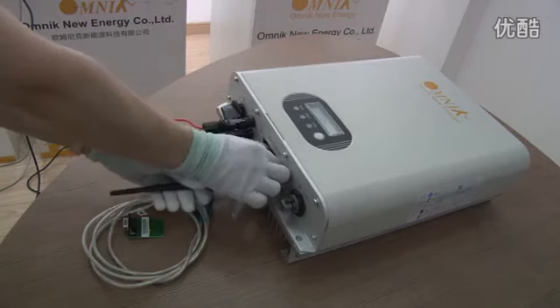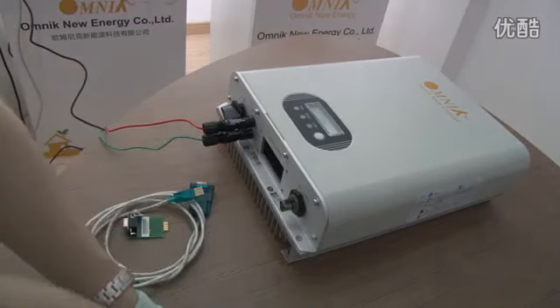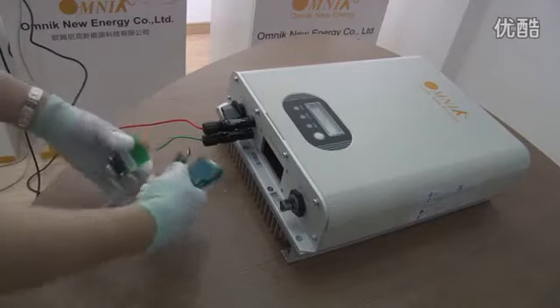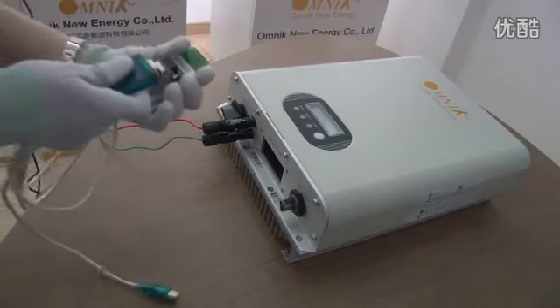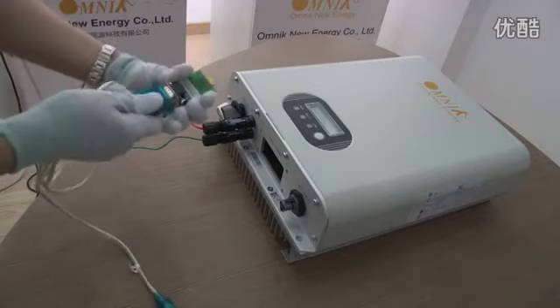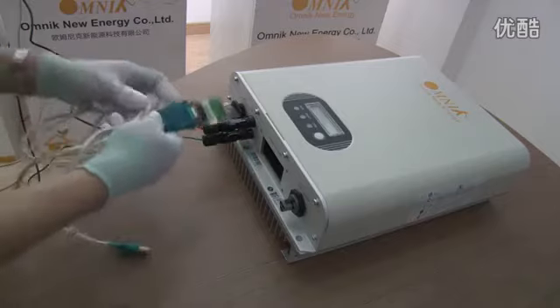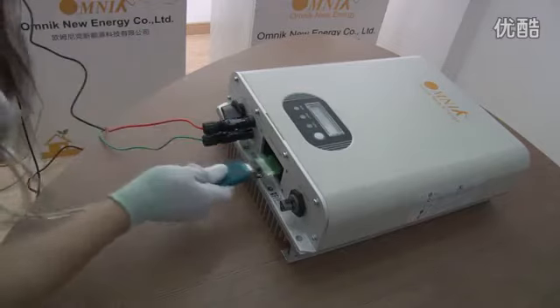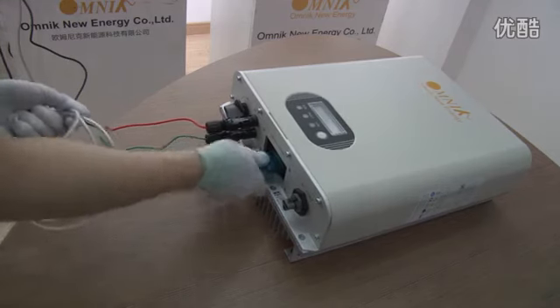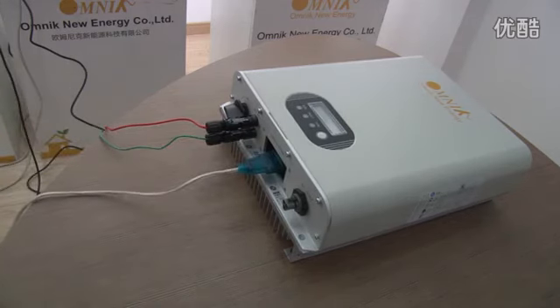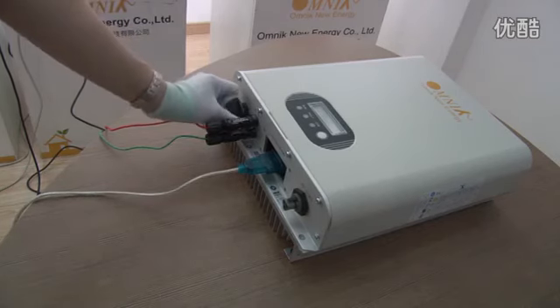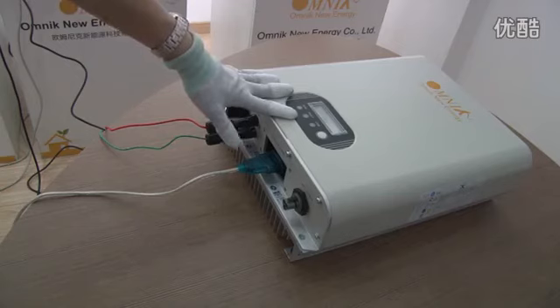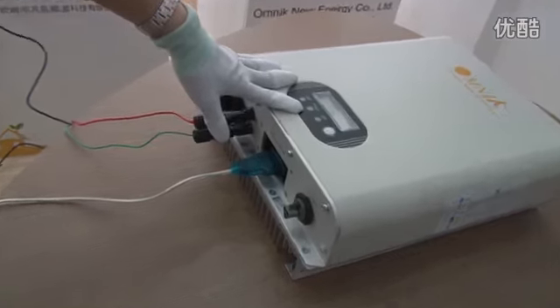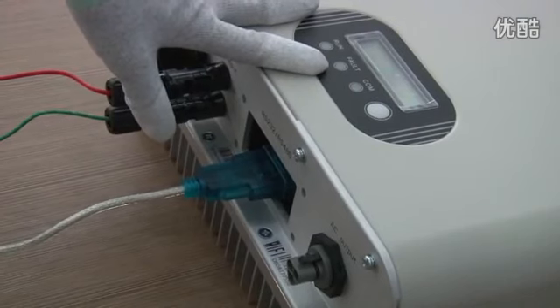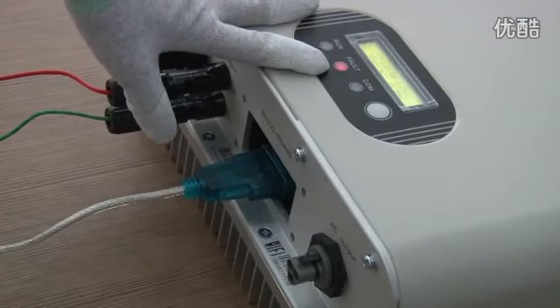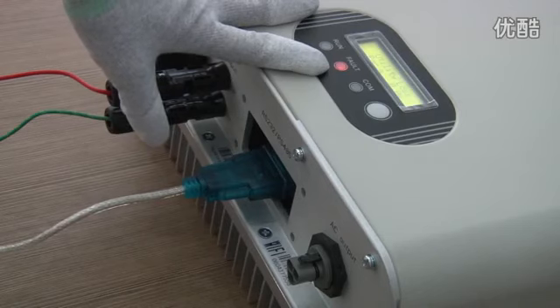Gently remove the Wi-Fi cord and put it aside. Connect the RS232 cord with the cable and insert it into your inverter. Then connect the USB to your laptop and turn on the DC switch. Wait until the red light's on, and the following procedure will be done on your laptop.